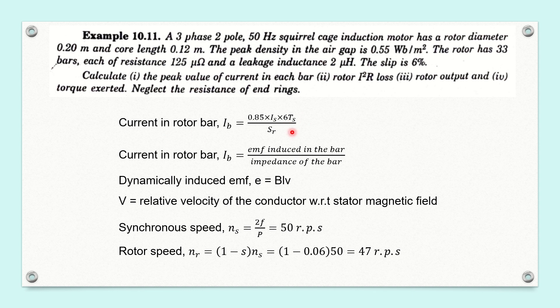We have to think of the next alternative — how can we calculate the current in the rotor bar? We can simply apply Ohm's law. We know that current flowing through any conductor can be calculated as I = V/R, or if we are dealing with AC, I = V/Z. So here we can calculate the current in the rotor bar as the EMF induced in the rotor bar divided by the impedance of the bar.